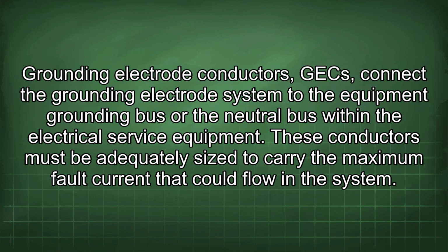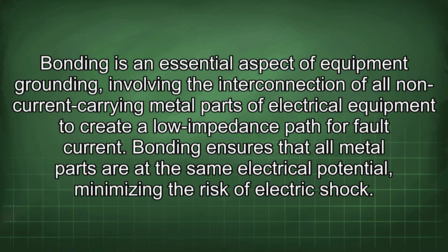Grounding electrode conductors (GECs) connect the grounding electrode system to the equipment grounding bus or the neutral bus within the electrical service equipment. These conductors must be adequately sized to carry the maximum fault current that could flow in the system. Bonding is an essential aspect of equipment grounding, involving the interconnection of all non-current carrying metal parts of electrical equipment to create a low impedance path for fault current. Bonding ensures that all metal parts are at the same electrical potential, minimizing the risk of electric shock.